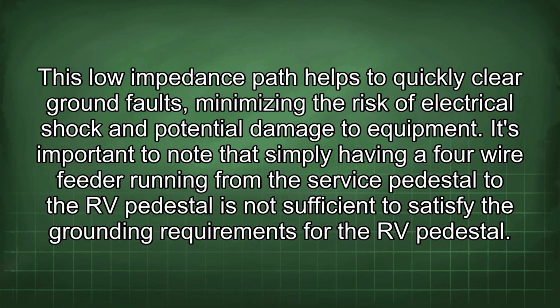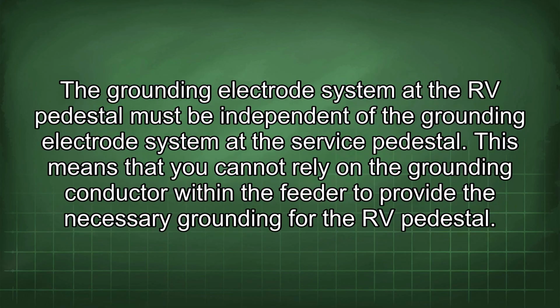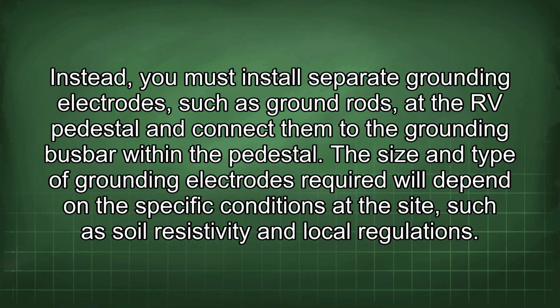It's important to note that simply having a 4-wire feeder running from the service pedestal to the RV pedestal is not sufficient to satisfy the grounding requirements for the RV pedestal. The grounding electrode system at the RV pedestal must be independent of the grounding electrode system at the service pedestal. This means that you cannot rely on the grounding conductor within the feeder to provide the necessary grounding for the RV pedestal. Instead, you must install separate grounding electrodes, such as ground rods, at the RV pedestal and connect them to the grounding busbar within the pedestal.